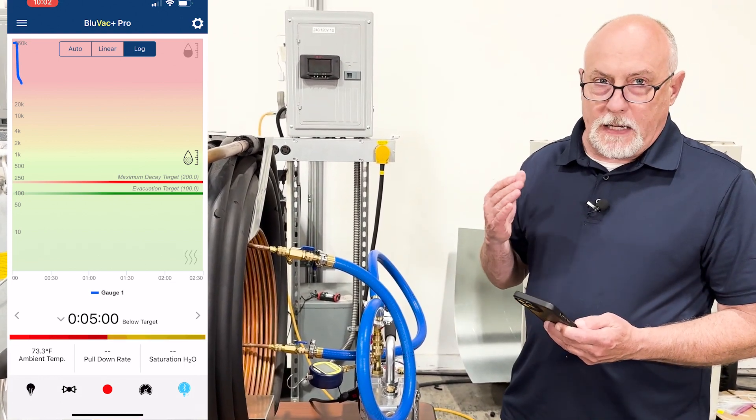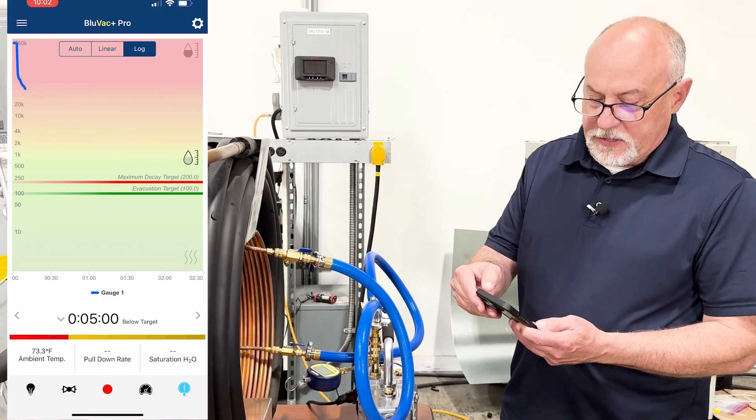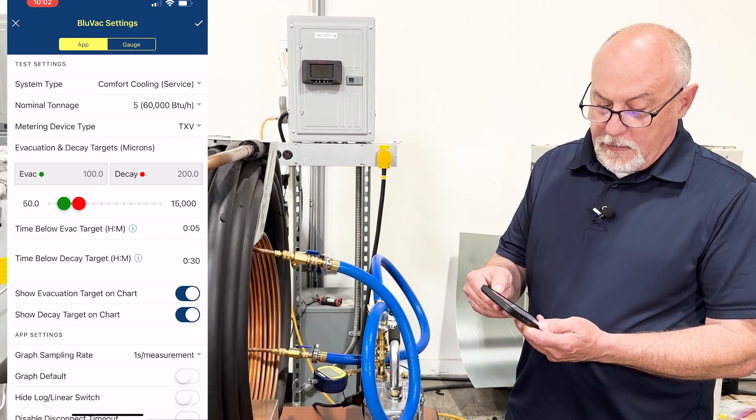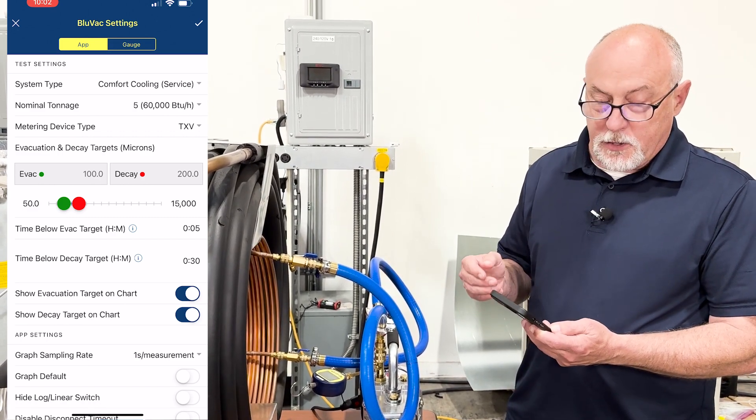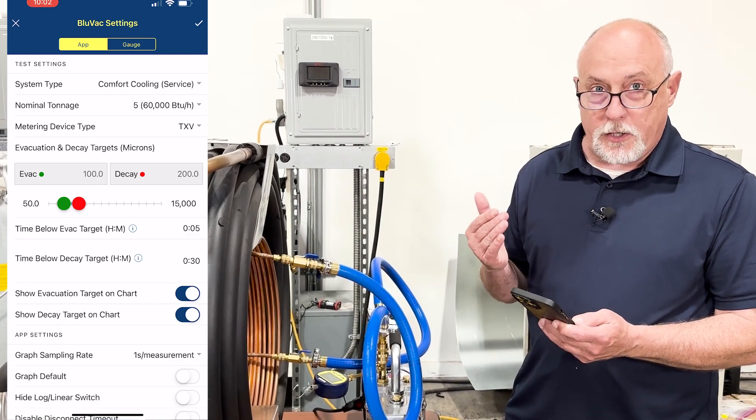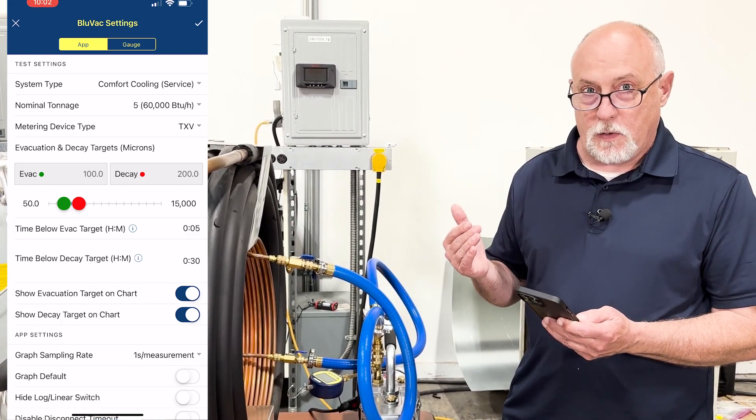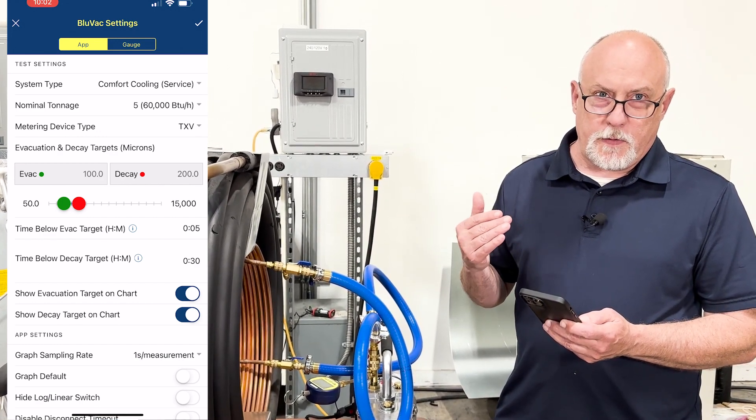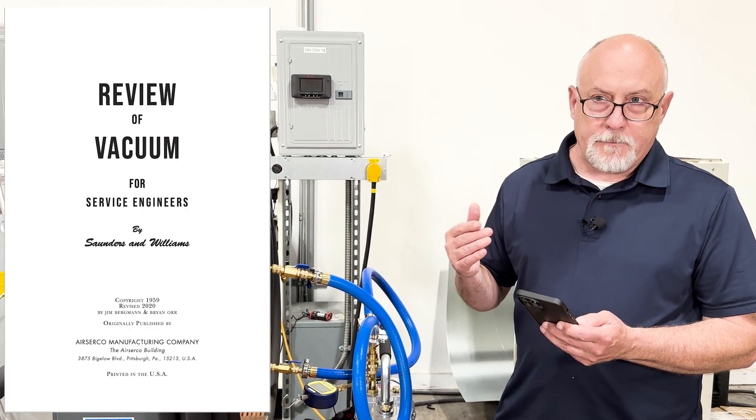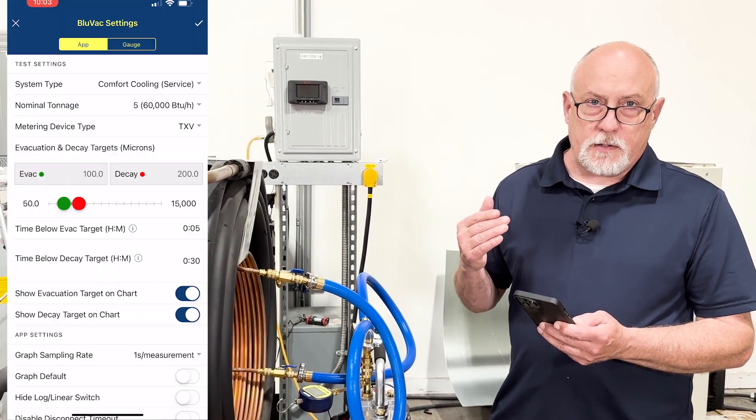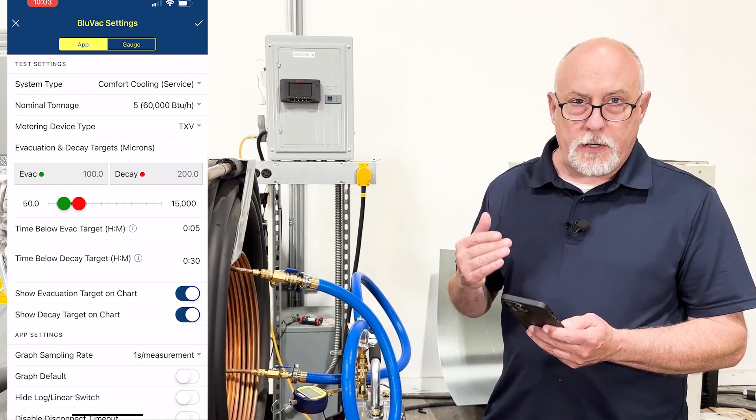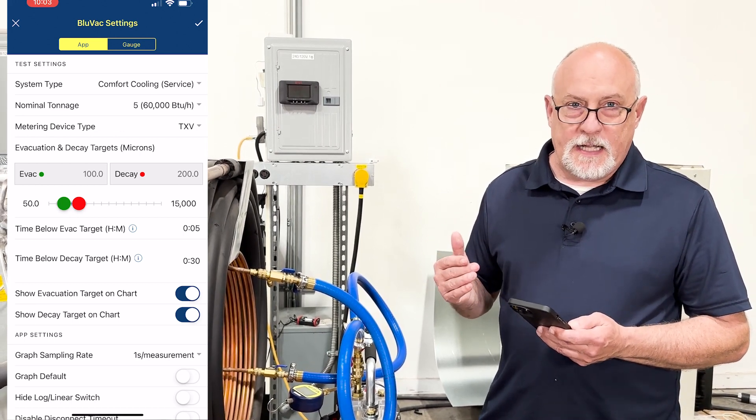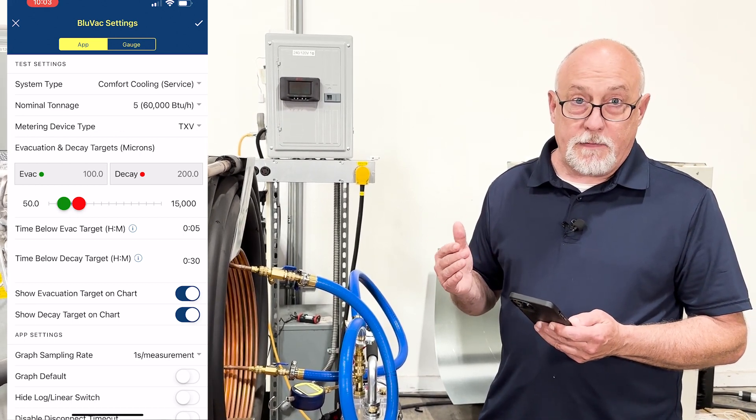This is going to pull down very quickly. Let's just go over settings now while this is coming down. I have this set up for a comfort cooling service for five tons with a TXV. And you'll notice I have my evacuation target set at 100 microns and my decay at 200. If we go all the way back into the 1950s and you go to the review of vacuum for service engineers, which I'll point out in the guide here, 100 microns was an ideal pull down with between 100 and 200 for ideal finishing vacuum. And you go, well, how do we get away from that? Why are we at 500 and 1000? And it's because we've literally forgotten how to do evacuation as an industry.